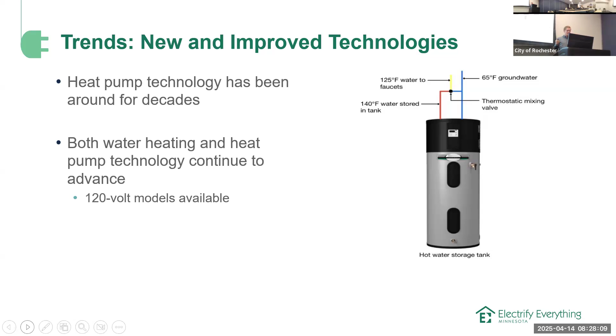There are also more and more product options available on the market. A big one now is 120 volt heat pump water heaters. These are a great option for customers who have a constrained panel or don't want to pay the upfront cost of doing 240 volt wiring. We're seeing that installing a larger 120 volt heat pump water heater with a thermostatic mixing valve is a way to provide a great low cost water heating solution for families with between 2 and 4 members. These are just a couple of examples—there's a lot more out there, but it's a constantly improving technology.